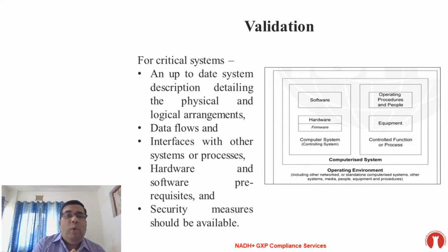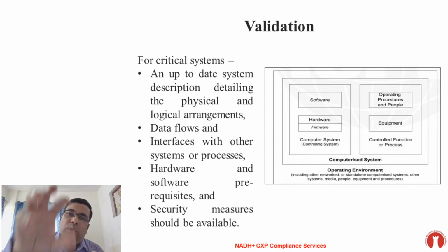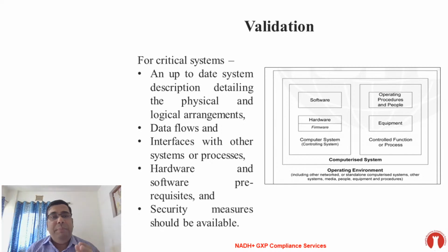Many people miss this hardware qualification during the validation activity. Let me tell you one thing. If you develop the software and the software is installed in your computer, that means you should not only validate the software, but you have to consider the hardware. If you are not considering the hardware, your validation is incomplete. Validation of hardware is a very simple activity, but many companies are lacking in that because they only follow the documents received from the vendor and just execute them. So physical arrangements are very important.